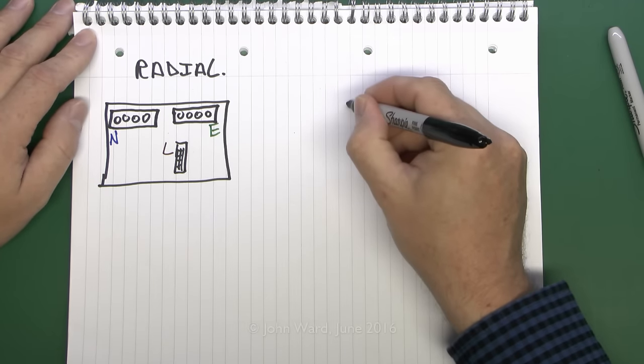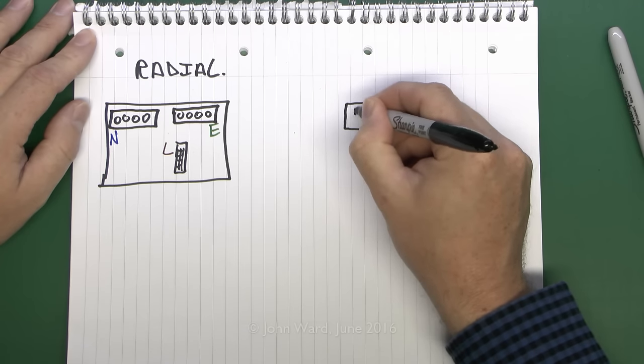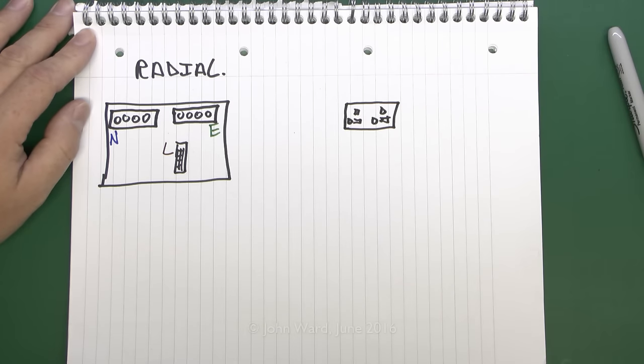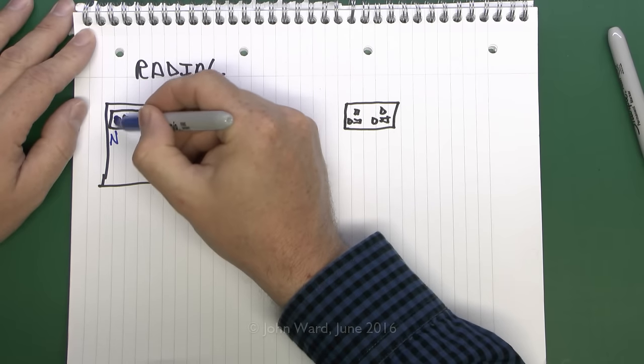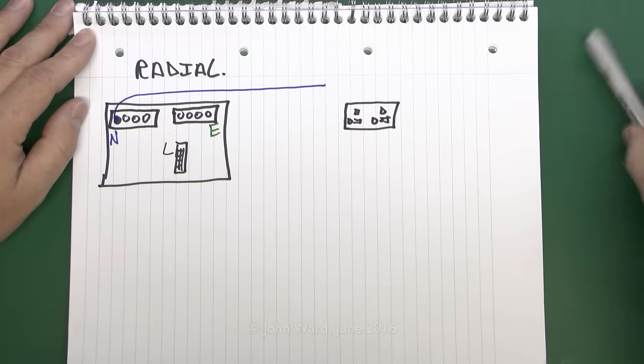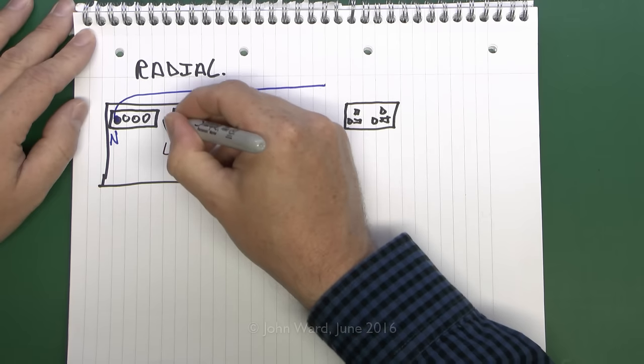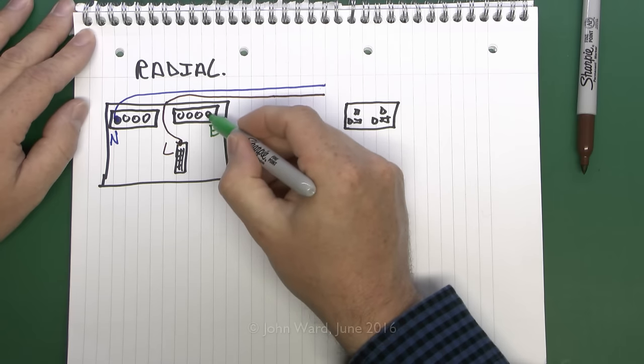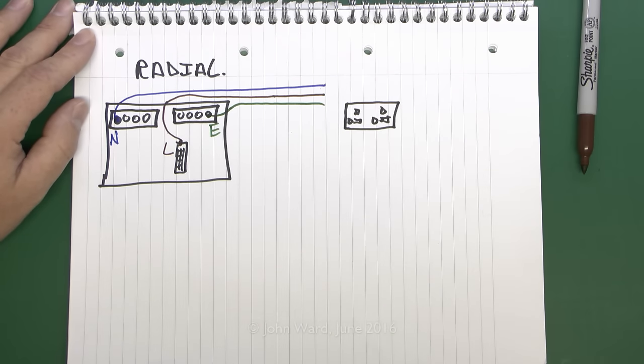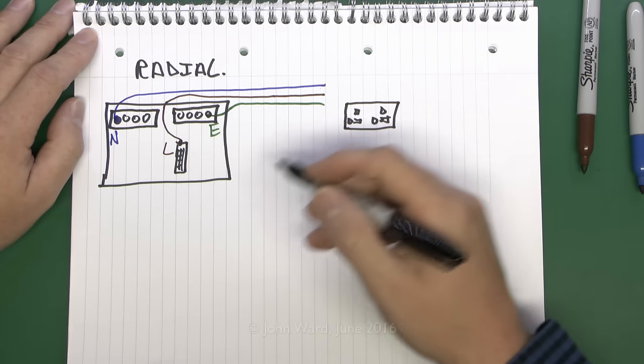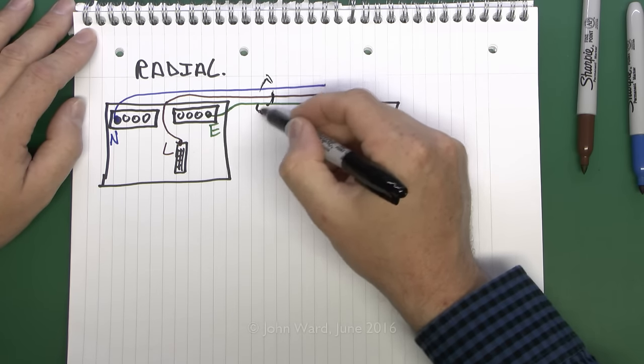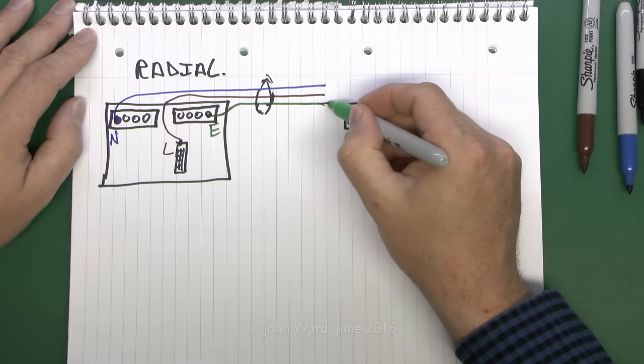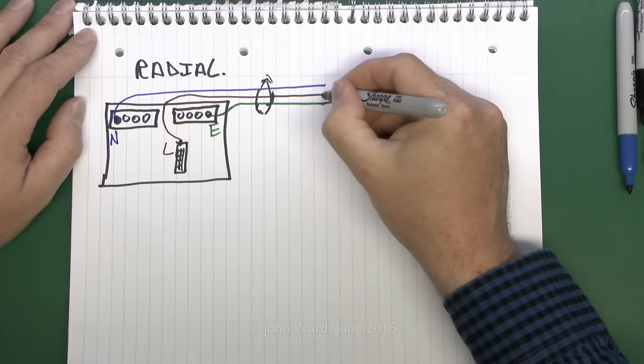The simplest possible option is just to have the cable coming out of there and going to a piece of equipment — say for example a socket outlet, a double socket. Your cables would come out of the neutral and connect onto the neutral bar. The line of course will be from the top of the circuit breaker, and the earth would come off the earth bar as well. Normally those would be contained within a single cable, although you could use singles in conduit. So essentially that's going to be a single cable, and these wires would simply connect into the socket outlet.